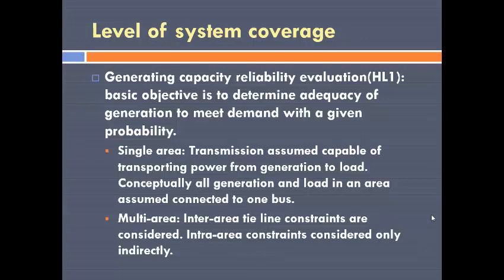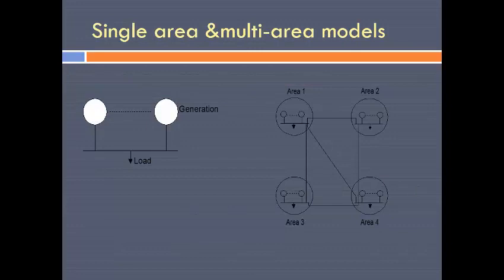The generating capacity reliability, or hierarchical level one, can be subdivided into two parts. One is the single area reliability evaluation. In the single area reliability evaluation, we assume that the comparison is between the generation and load, and the transmission is assumed to be capable of transporting power from generation to load. Conceptually, all the generation is connected to a single bus and all the load is also connected to a single bus.